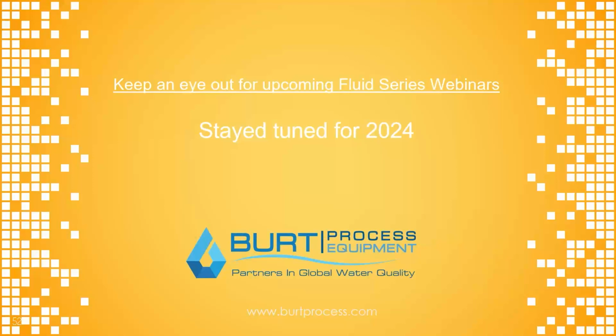And Mark Ellison had a question about the high voltage needs and why, or in what scenarios, you would need high voltage equipment. The high voltage is typically utilized because of the actual system in there. Generally the HVAC, now you can get 460 volt HVAC, but a lot of the HVAC systems are not. They'll either be 208 or 120 volts. But very often it's the actual equipment in the actual system that needs that 460 volt, the pumps, the agitators, and things like that. But obviously, if you don't have that requirement, then you can adjust the voltage down for these systems.